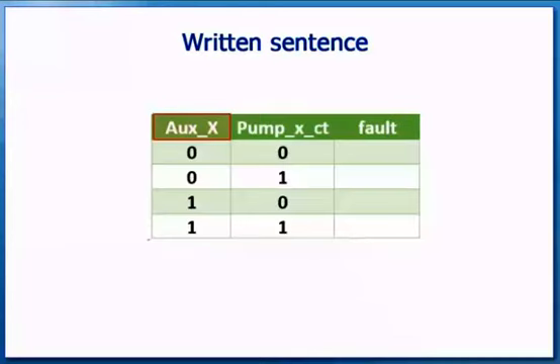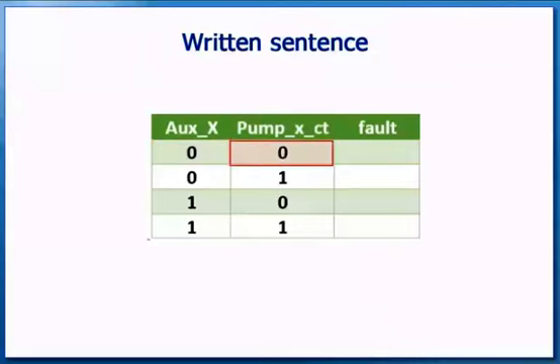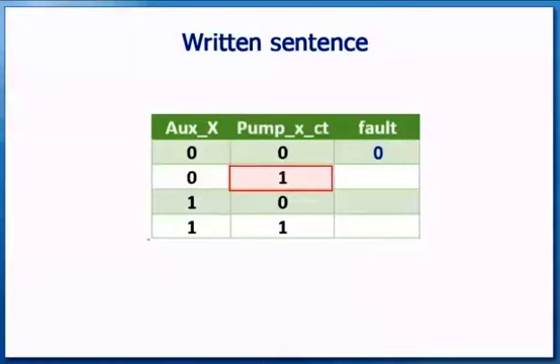There is AUXX to indicate when PUMPX is switched on, and PUMPXCT indicates that PUMPX is running correctly. We can use a truth table to show the possible combinations. If auxiliary X is off and PUMPXCT is off, then this isn't a fault — we show a 0. If auxiliary X is off and PUMPXCT is on, then this is a fault — we show a 1.